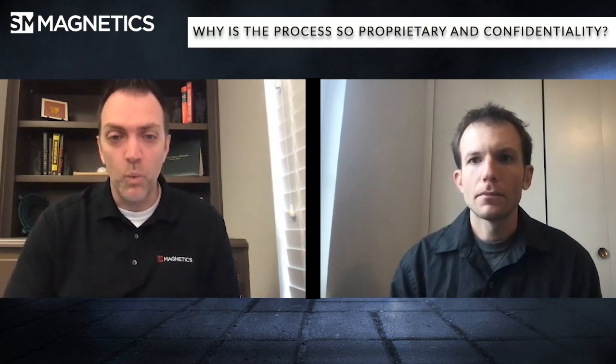The parylene process is very proprietary and confidential — why is that, and what are the alternatives for customers who need to audit a facility that does parylene? Everybody has their own process, which is why it's proprietary — it's not a standardized process. Everybody has found the best way to get that uniform coating for their application. While the machines are pretty typical, the exact program they use — the time cycles and temperatures — is very proprietary and protected. They're probably not going to tell you the exact details, but it'll be documented in a general fashion to make it repeatable. If you're switching parylene facilities, you're going to want to do a lot of testing afterwards to make sure you don't have pinholes and that you have uniformity.